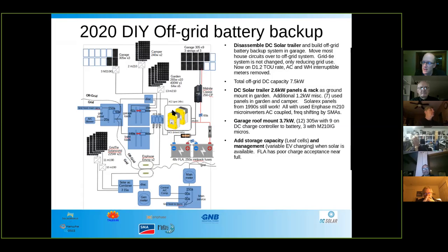When the state of charge is low, depending on how you set things, the Sunny Islands can connect to the grid on this other AC input. Inside the inverter is just a relay, and first they synchronize this AC waveform with what it sees on the grid side. When it sees that they're matched up, it closes the relay, and everything is connected to the grid at that point. All of your loads are connected to the grid.